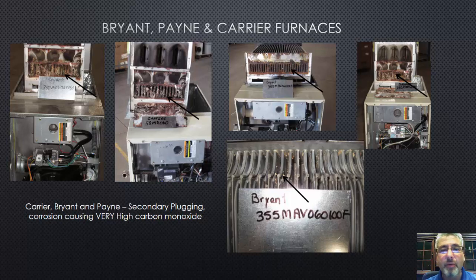But here's the deal, really simple: 40 inches tall. So if it's 40 inches tall and looks similar to this, you know you're on the right track, and you know that's the series of that furnace. They don't make this secondary anymore in their new furnaces - their new furnaces use a completely different secondary heat exchanger. So once these have all been retired, you won't have to worry about it.